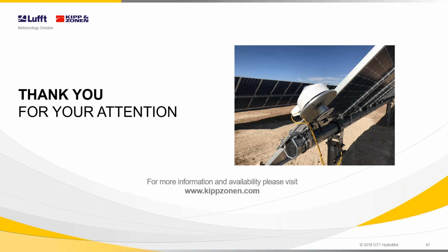Off the top of my head, I would not know the exact number, but it depends on the size of the plant. So if you have below 40 megawatts, then the IEC has as a multiplier 2. So that means, if I get it correctly, that you would have 2 albedo meters.